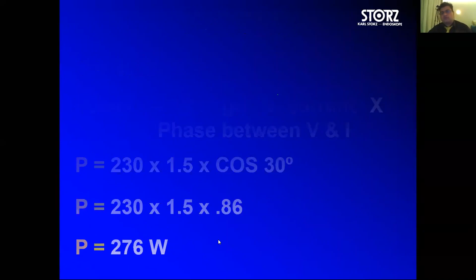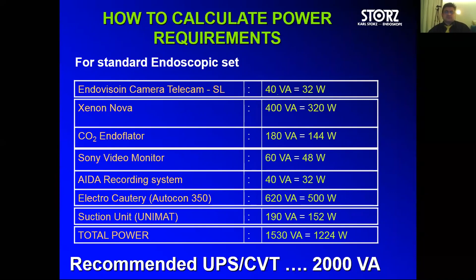So for a surgeon not to get too technical in calculations, we have standardized it, and you can see that an Endovision camera approximately takes 40 VA, volt-amperes, and when you do that multiplication, the wattage comes. So finally, when you add up a video trolley, your total power consumption would come around 1530 volt-amperes or 1223 watts. So you take a higher rating, and if you are planning to add more equipment, you take the next level of UPS or constant voltage transformer, which could be 1.5 kilovolt-amperes or 1500 volt-amperes, or 2000 or even higher. That's how you calculate the rating.